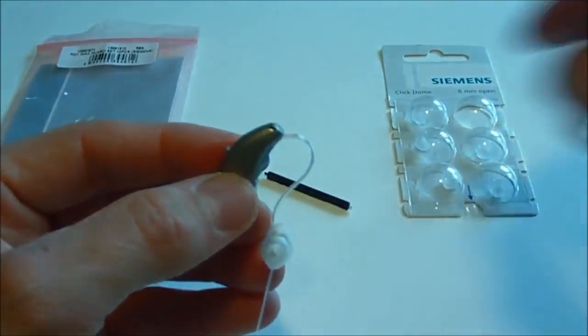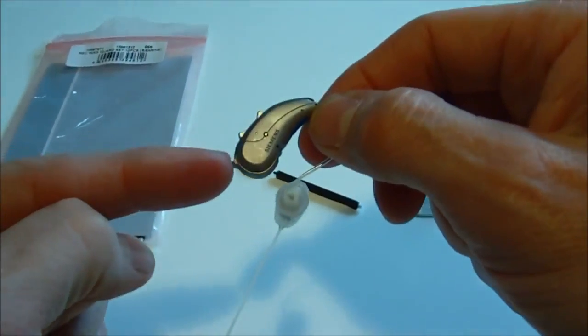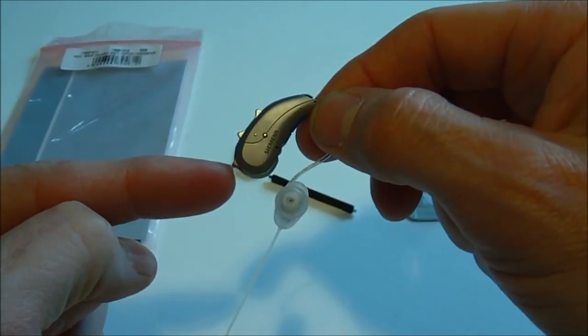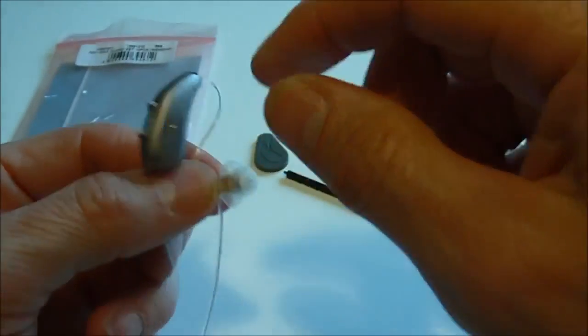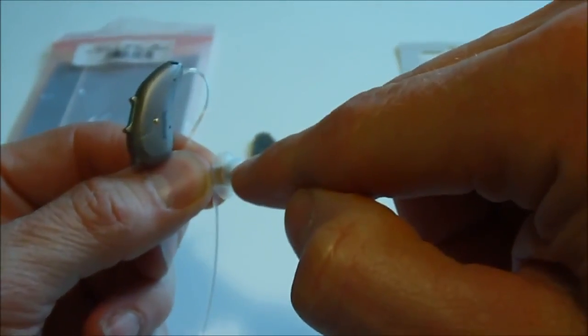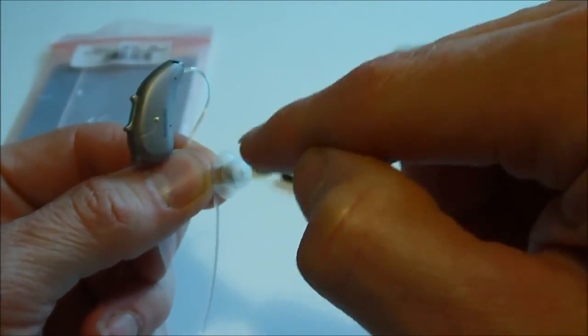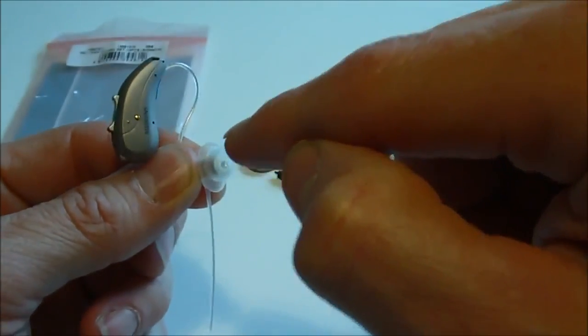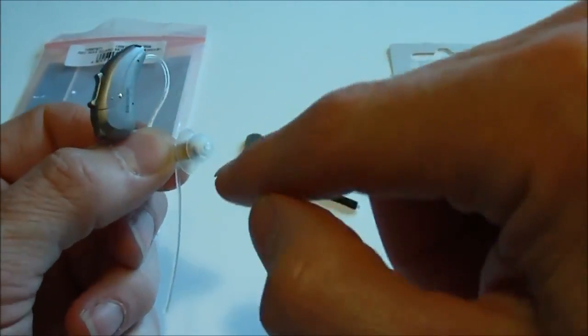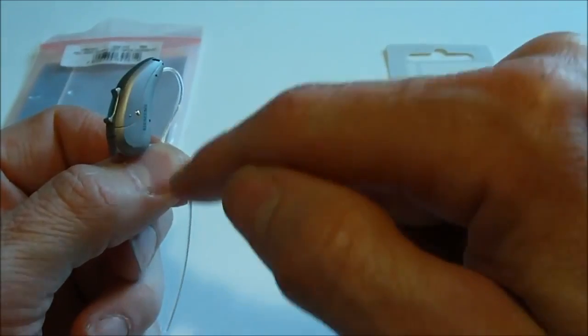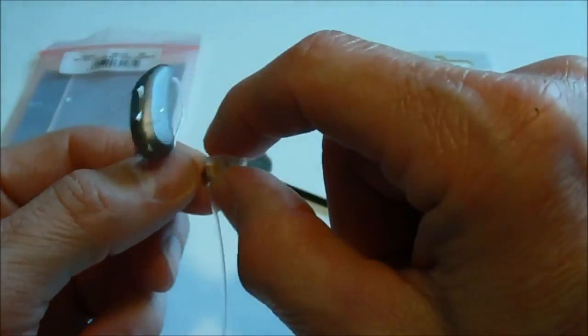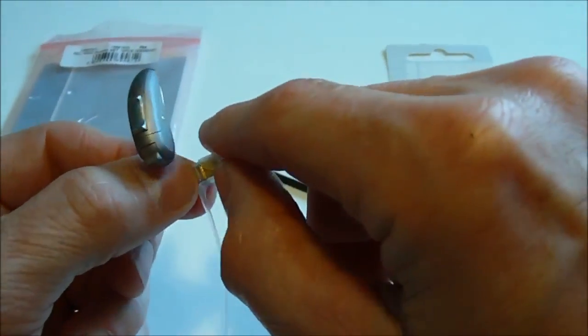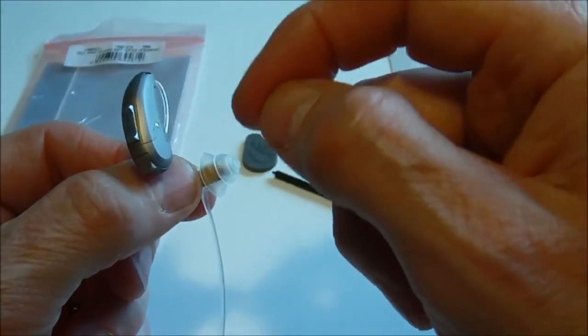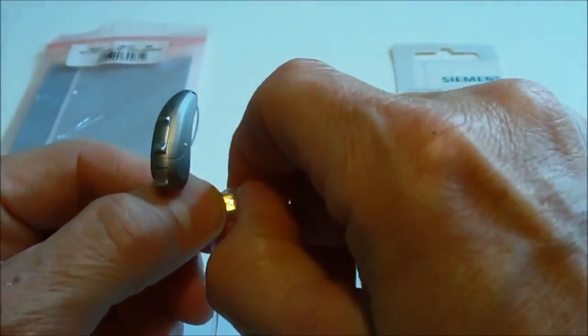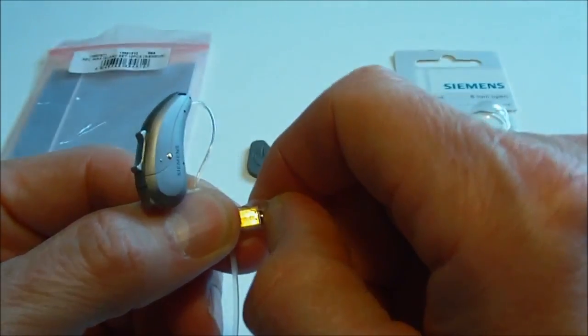Now, if the hearing aid is not working, change the battery. When you put a new battery in, you should get a start-up tone come out of the speaker. So if you put that to your ear quickly, you will hear the tone. If you don't hear the start-up tone, then you really need to take the click dome off because it may be blocked underneath. In order to take this dome off, you need to get your nail into the groove just on the end of the speaker.